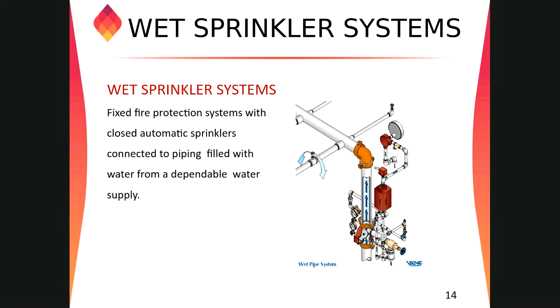You can see in this figure, right? This is a general schematic of a wet sprinkler system. We have connections from the underground fire water network, all the way. There is a T connected to a riser. Here we have the isolation valve, which we need for maintenance. We can close it and do the maintenance, and then we have the alarm check valve. At the bottom of the alarm check valve, we have a main drain valve, and we have the fire department connection soon after the alarm check valve, and a water flow alarm system, right? So this is the most common worldwide. We can use it where there are no chances of freezing.